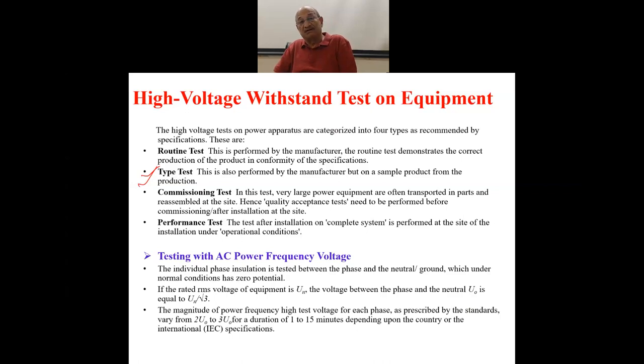So the high impulse voltage tests are also included in the type test, where you take some sample randomly and test it with impulse voltage application to ensure that the traveling waves, overvoltage traveling waves, do not damage the insulation.